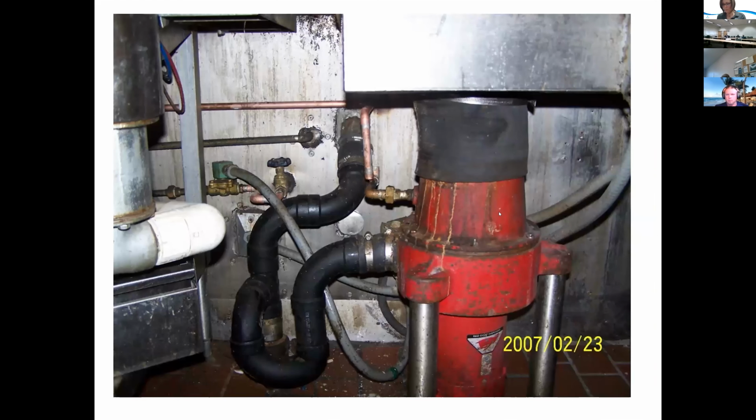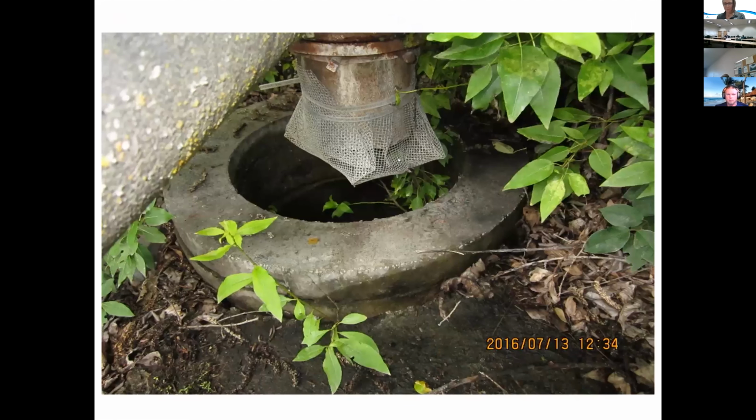Yeah, I don't know why we love these so much. This is a garbage disposal. So when the garbage disposal comes on, the solenoid opens and water flows through here. It's not okay. Actually, this had been corrected, but I took the picture anyway because it was a lot of fun. Lots of stuff will get connected because they just don't know that backflow can happen. Air gaps, lots and lots and lots of air gap problems in the world.